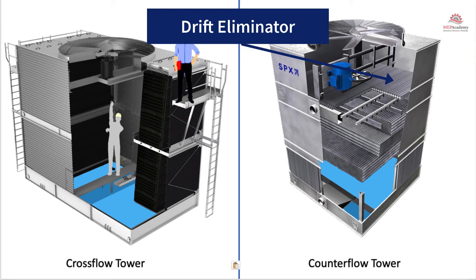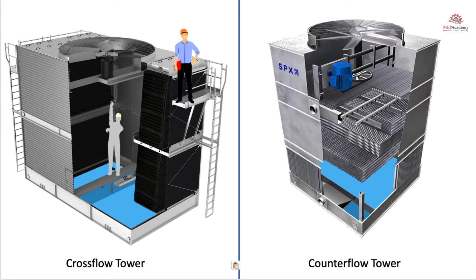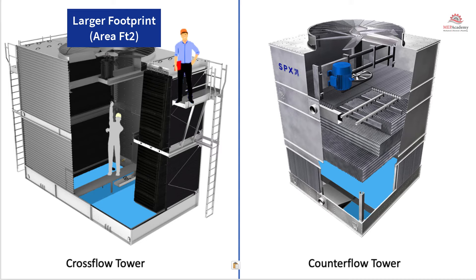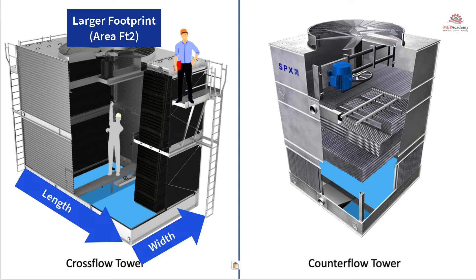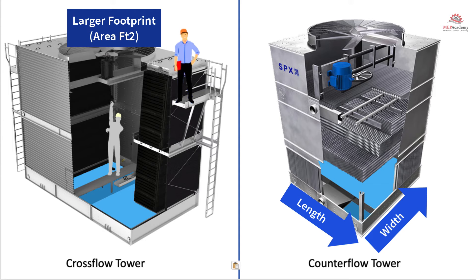Because we lose a little water, we'll need a makeup water pipe connected to the cooling tower to bring in additional water lost to evaporation, blow down, and drift. The cross flow tower usually takes up more area — the length times width is much greater for the same tonnage compared to the counter flow.